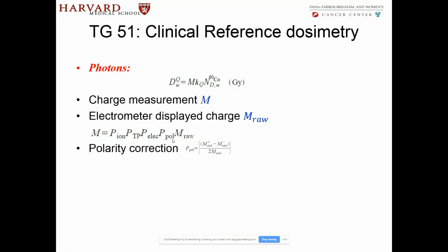So polarity correction, what that says is, look, on the ion chamber, you have a positive and a negative voltage applied to the two electrodes. And when ionization happens, the positive and the negative ions get collected on different electrodes. Well, does your system actually care about it? So you take a value by having one electrode giving positive voltage, the other one negative, do a measurement, that's M raw plus, then flip the polarity, do a M raw minus, take the difference and divide by the mean of the two. That's the polarity correction that you have to apply.